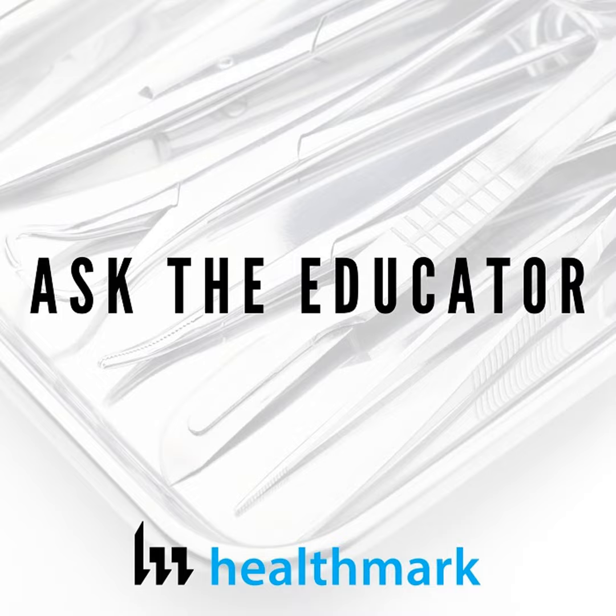So when you're at the sink cleaning these, it's one of those things, just like flexible scopes. I think the message has been put out about flexible scopes: hey, we need to take time to do these. We're still seeing infections and problems with flexible scopes, but in general the understanding is there that these are complex devices and they need to be looked at. I don't see that with shavers.